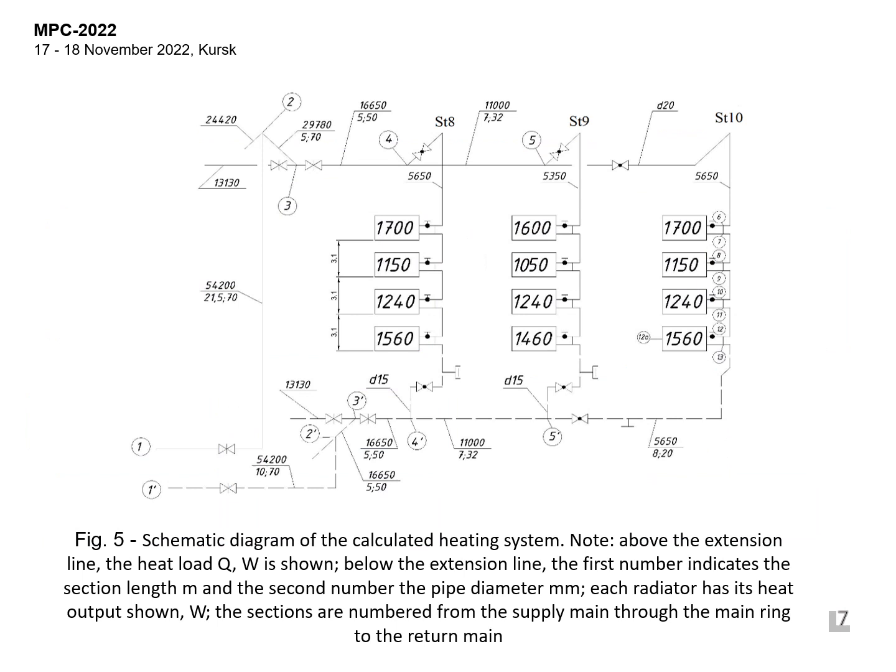Let us calculate a single-pipe heating system with one of the branches shown in figure 5. Calculation of heating pipes will be carried out by the method of dynamic pressures. As the most unfavorable ring, we take the circulation ring including standpipe 10. Let us calculate the same branch of the heating system using several existing hydraulic calculation methods in order to compare the final results. Accordingly, the input data for the following methods will be the same as for the dynamic pressure method.